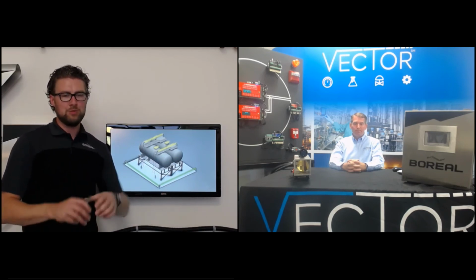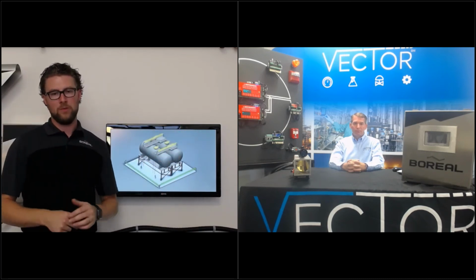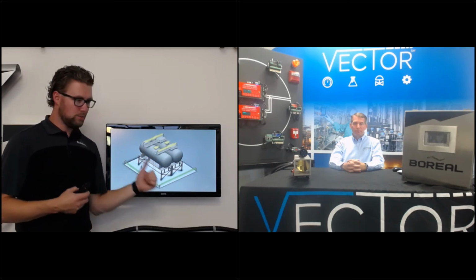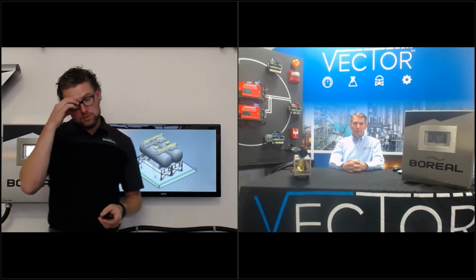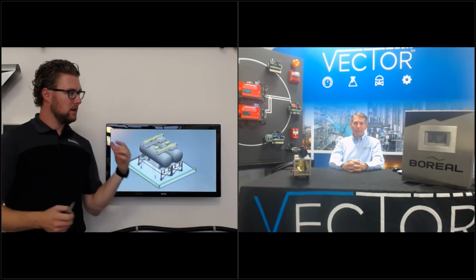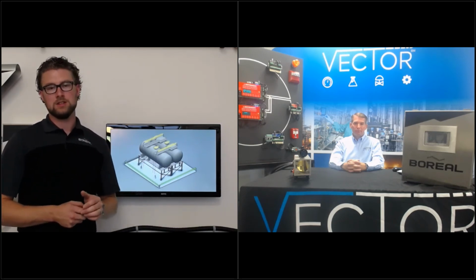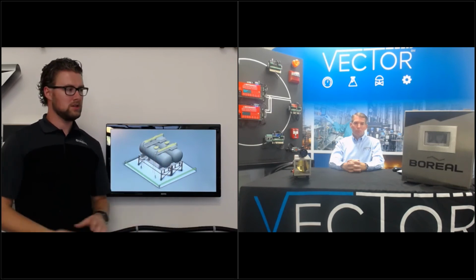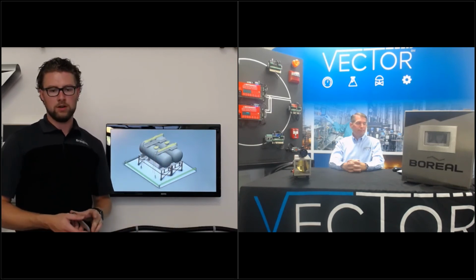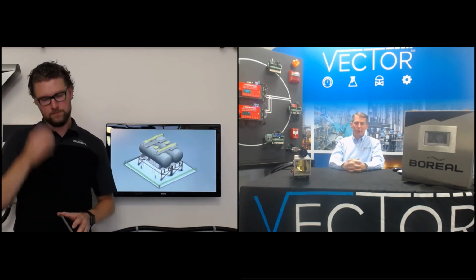And there always seems to be kind of a background concentration of ammonia in and around pumps, flanges, compressors, anything else like that, where with our particular technology, you can expose it to as much or as little gas as you like without having to worry of poisoning, consuming, fouling, or degrading the performance of your system. So for ammonia, TDL technology is as good as it gets and is the ideal premier technology choice for ammonia monitoring and detection. Yeah. No oversaturation, no having to replace sensors.